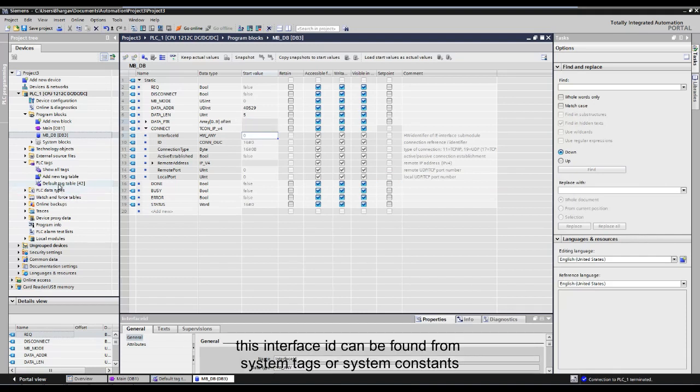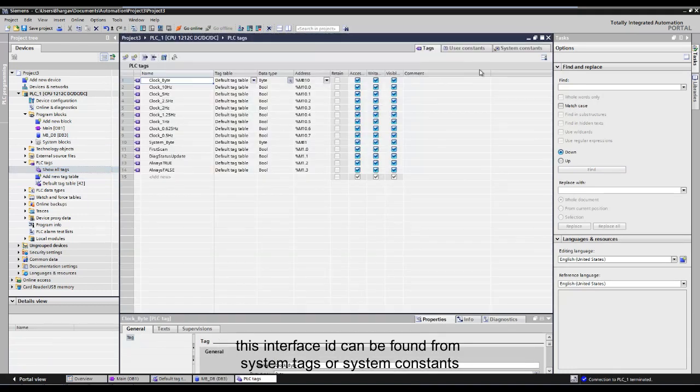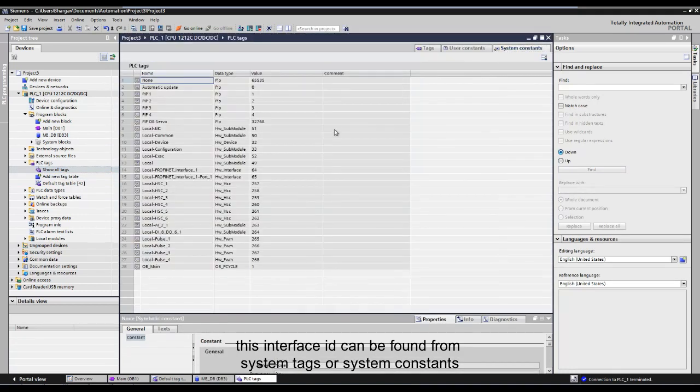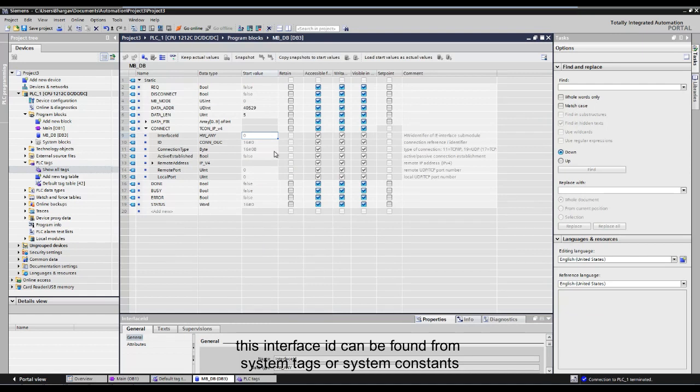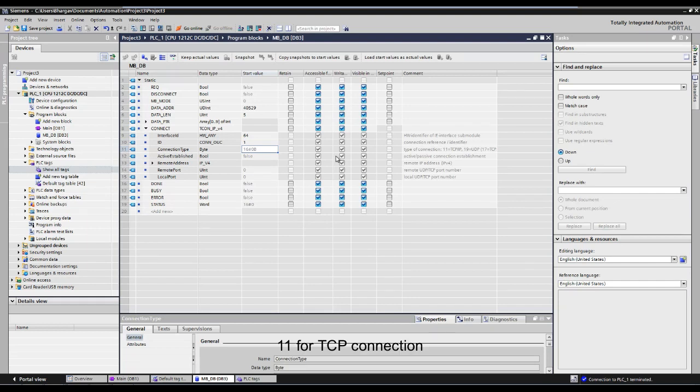This interface ID can be found from system tags or this system constants. And in our case, it is 64. This is unique ID for each connection instance. You need to take care if you have defined this MB client block multiple times. 11 for the TCP connection.